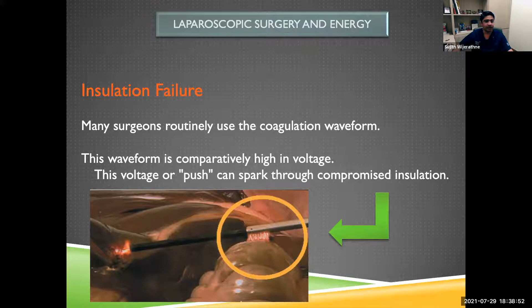So why I say that is because, as you can see here, if this surgeon is using this at a targeted site, but the insulation is not intact, the current will find another pathway to leak out and then get back into the ESU. So this way, there can be thermal injury to bowel, or any other organ, which you may not even see. This is an important thing we should look for, especially in institutions and places where they do not have these new machines which can check properly for insulation failure.